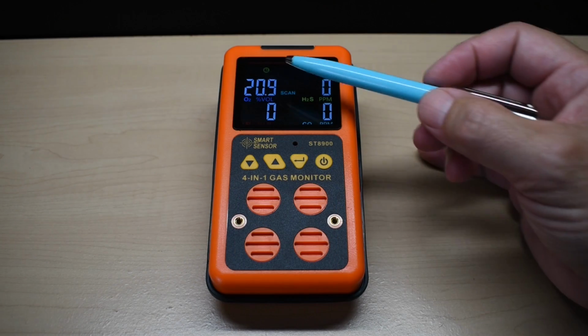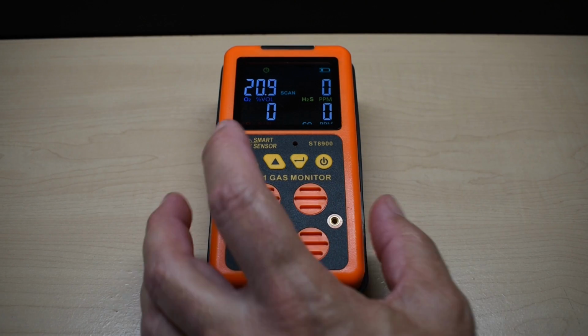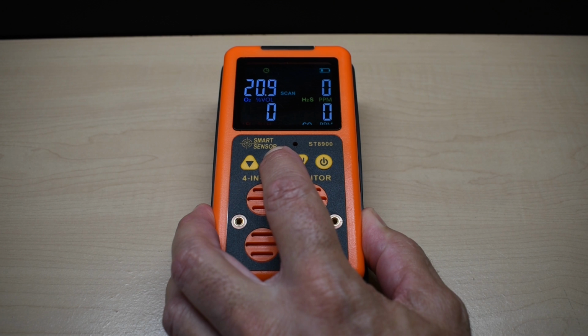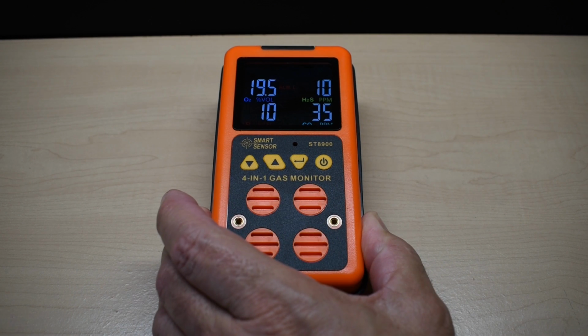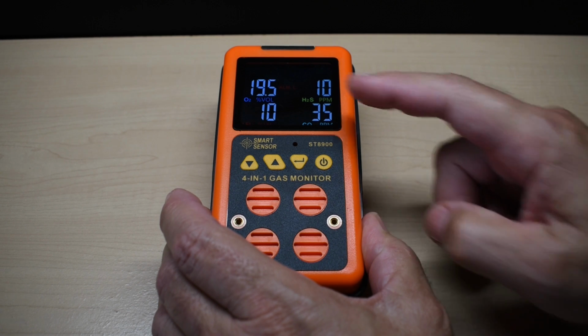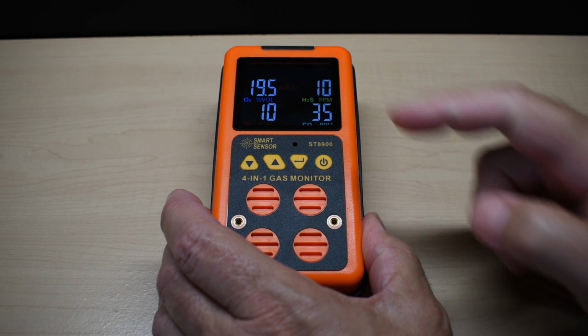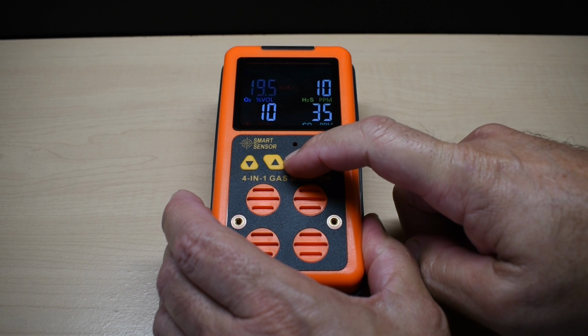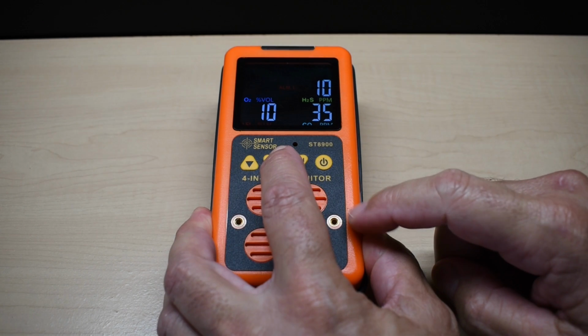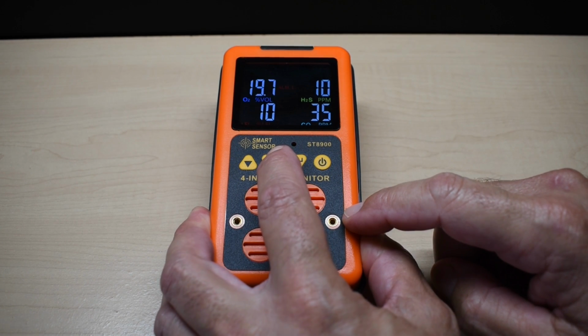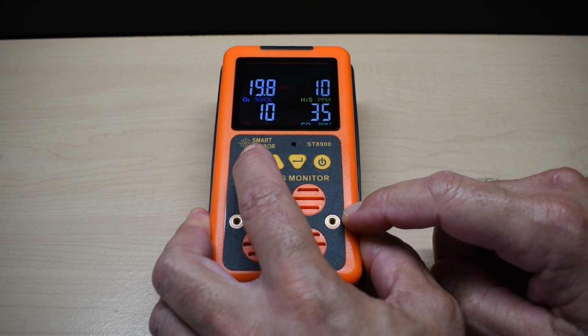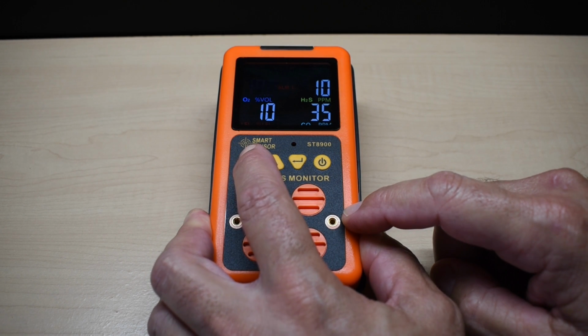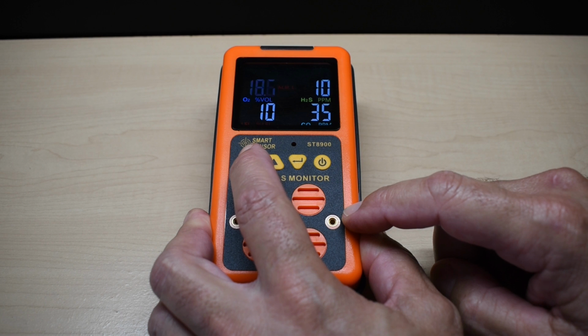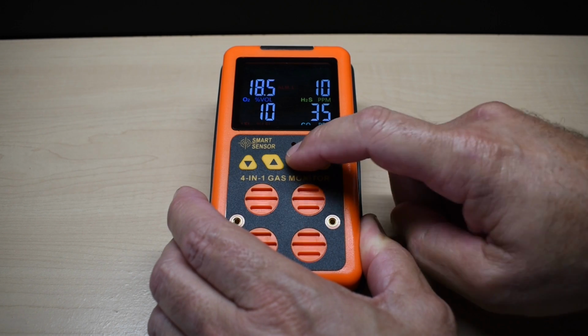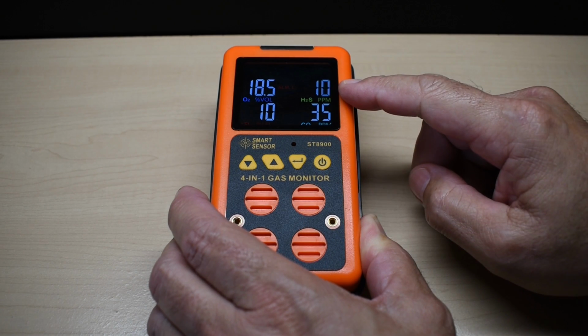Now let me show you how to set the lower and upper limit alarms. I'm going to push this right here for 2 seconds. Now it says ALM low. So if you want the oxygen alarm to trigger, you change it right there. You push enter, it's flashing, you can go up and down. I can make it trigger at 19.8, or bring it all the way down very low to whatever level I desire. So I'm just going to leave it at 18.5. Hit enter, and it goes here.